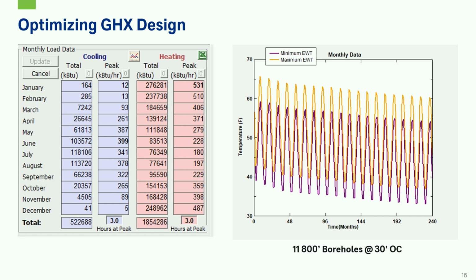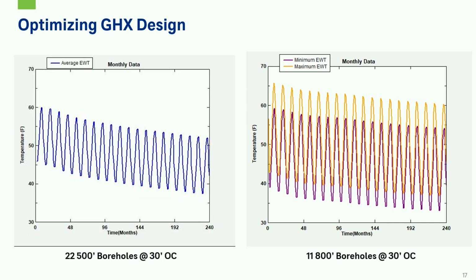So with those couple of parameters, keeping the spacing the same, and changing the number of bores and increasing the depth to 800, we saw a similar drift. Nothing really changed. We see the same pattern. It's maybe a little bit flatter, but you can see we have those same loads on the left, and we still see that thermal drift. We didn't change anything with our annual energy loads, so it really shows that it's important to make smart building decisions and capture those design decisions in the energy modeling. Because even though you can make small changes to mitigate the bore field, it's not going to be able to solve all of your load imbalance issues.